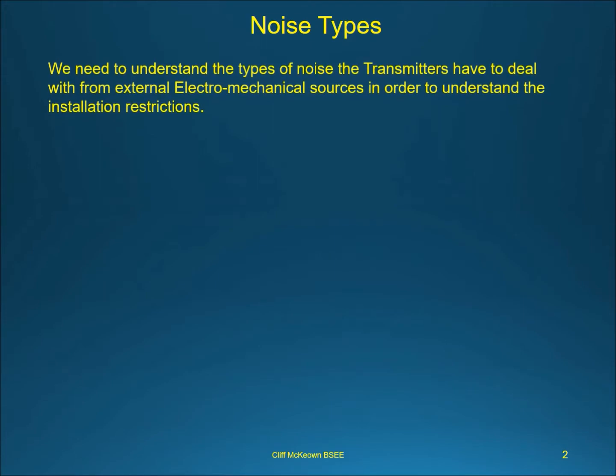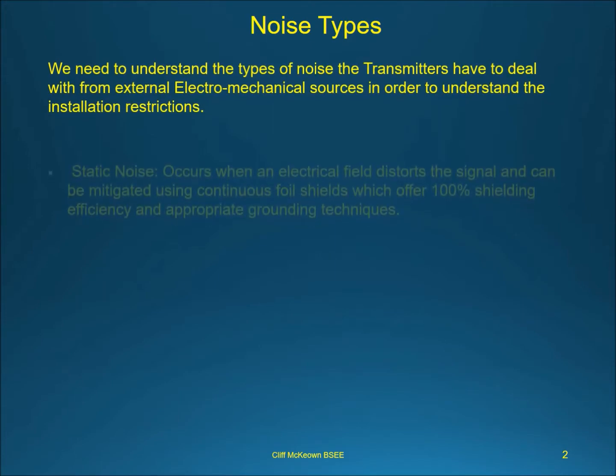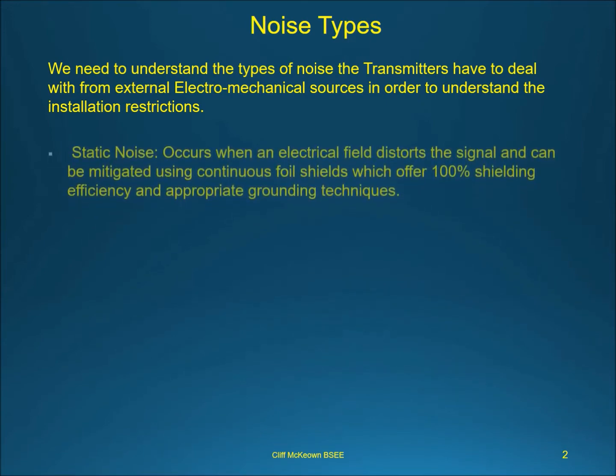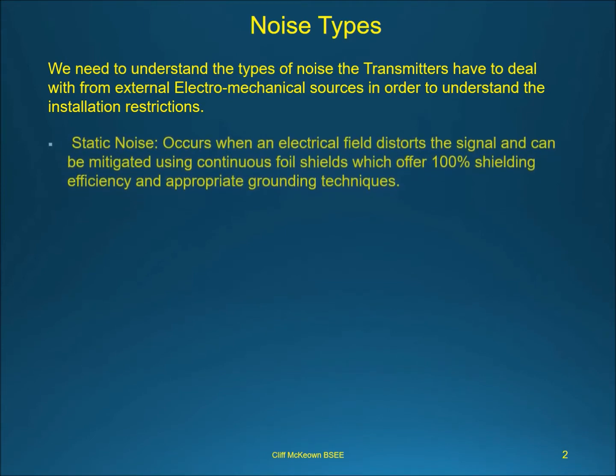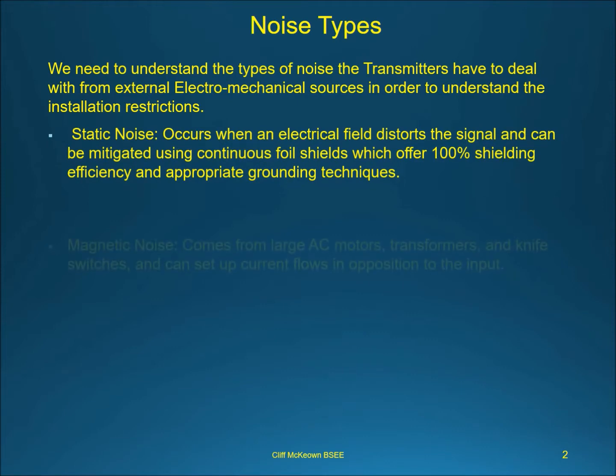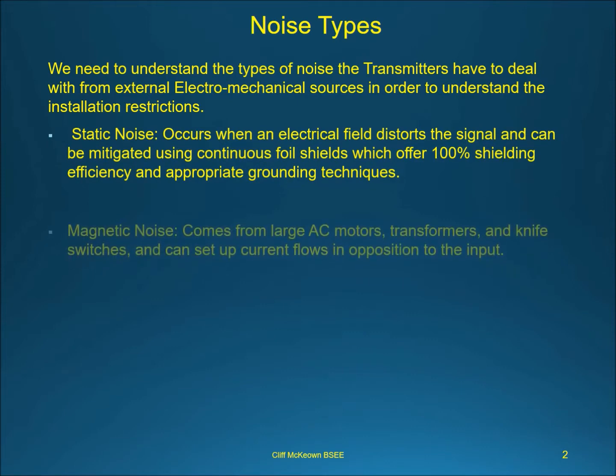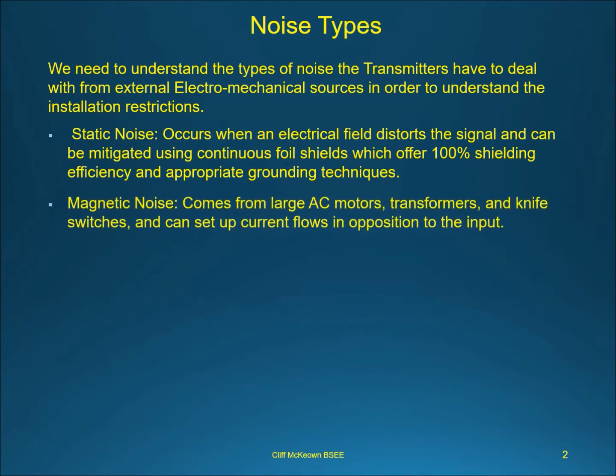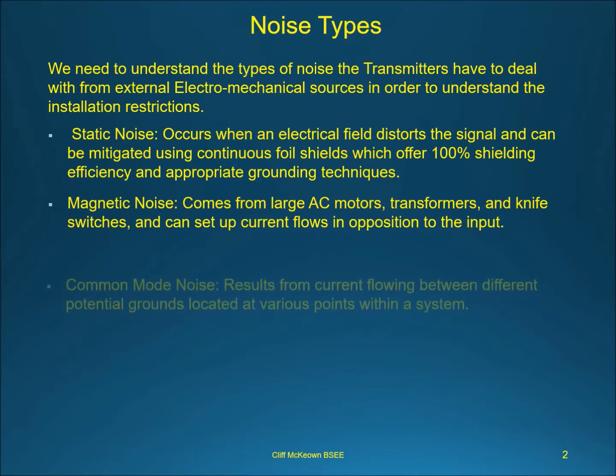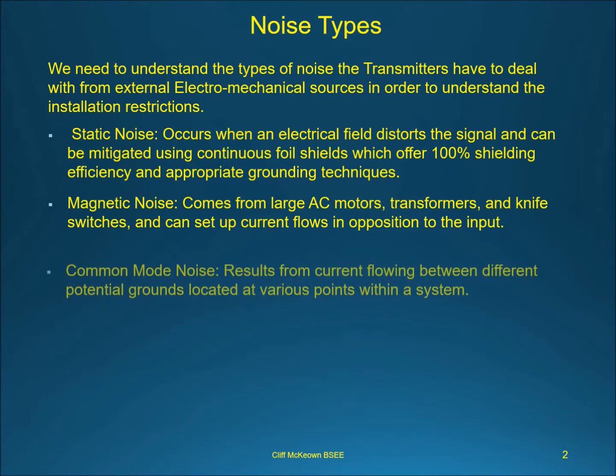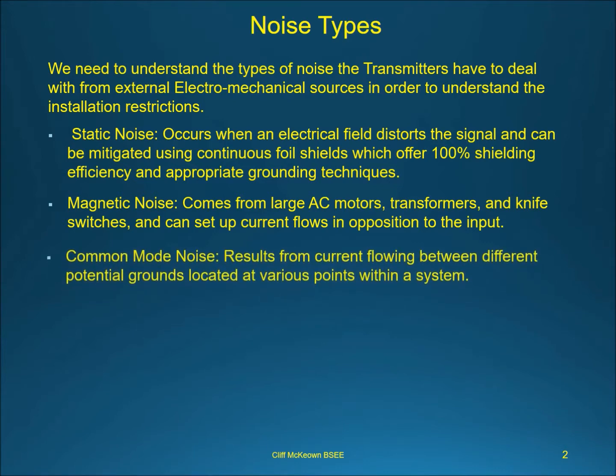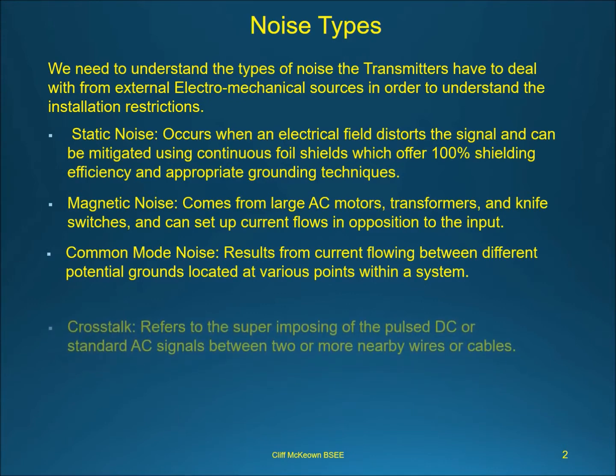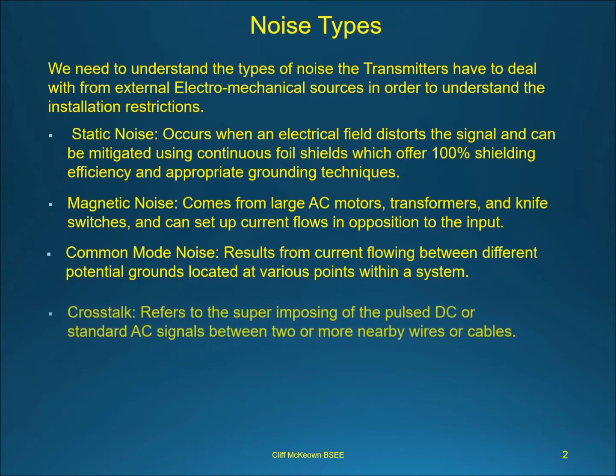Static noise occurs when an electrical field distorts the signal and can be mitigated using continuous foil shields which offer 100% shielding efficiency and appropriate grounding techniques. Magnetic noise comes from large AC motors, transformers, and knife switches, and can set up current flows in opposition to the input. Common mode noise results from current flowing between different potential grounds located at various points within a system. Cross-talk refers to the superimposing of the pulsed DC or standard AC signals between two or more nearby wires or cables.